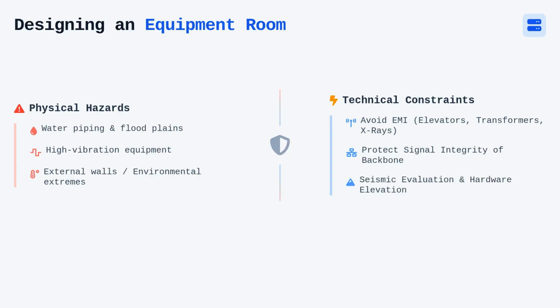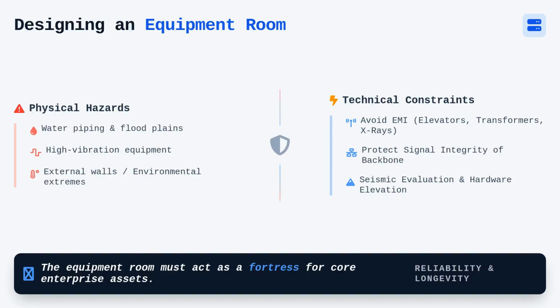Furthermore, structural integrity matters. We must evaluate the room's placement regarding seismic zones and ensure flooding risks are mitigated by elevating critical hardware. If the building is located in an area with a high water table or known flood risks, the equipment room must be positioned above the floodplain. A well-designed room acts as a fortress, protecting the core assets that keep the entire enterprise functional day and night.